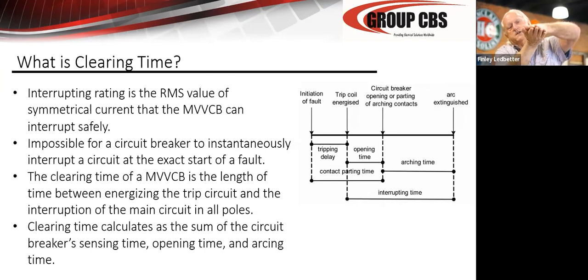The breaker contacts in the vacuum interrupter move a very small distance, let's just say 10, 12 millimeters. In that amount of time, at the next current zero crossing, which is less than one cycle, they will part. So you have the mechanical delay and the delay in the interrupter. Those two combined have to operate within 3 to 5 cycles, because they build a 3-cycle interrupting breaker and a 5-cycle interrupting breaker. Depending on your application, you will have received either 3-cycle or 5-cycle breakers. The majority of medium voltage breakers are 5-cycle opening devices, but every manufacturer does build a 3-cycle breaker.